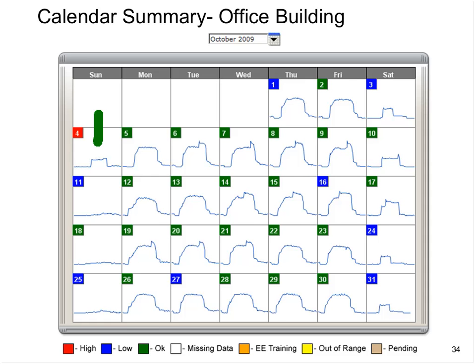And you're also probably asking, well, okay, Sunday has a load shape, but so does Saturday, and Saturday's a weekend. Why isn't that flat? Basically, what this customer did was decide to add another shift onto Saturday, and at the point they decided to add that extra shift, they rolled back their comparison baseline to include this. So Saturdays from the change on would look normal. That load shape would look normal on a Saturday. However, Sundays are still abnormal. There isn't a shift on Sunday, but still, I would ask what Sunday the 4th is all about.